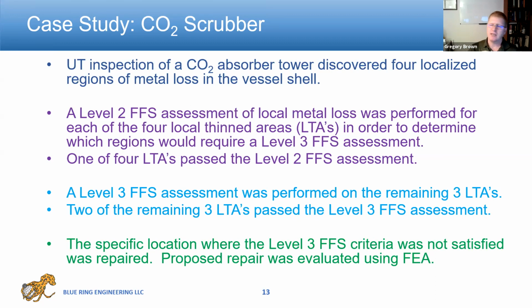I had to sanitize them to be shown publicly. So in this case, we had what's called a CO2 absorber tower. It's a tall, narrow pressure vessel, and it had regions of metal loss in the shell. There were 4 regions of metal loss, and an inspection was done to determine how much wall thickness was there. As it turns out, this metal loss was below the designed minimum thickness.